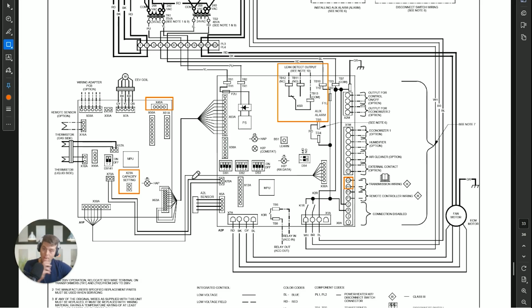And then you get over here to your A1P board. You got your expansion valve coil plugged in over here. You've got your sensors that are plugged in here, temperature, liquid side, gas side, remote thermistor if you had the option that you wanted to add to it. And then you've got your trusty capacity adapter because maybe you bought the wrong size unit and you want to change it on the fly, which, yes, you can actually do. Your A2L sensors down here in the bottom left-hand side. This is a 4-wire sensor that goes down to the bottom.